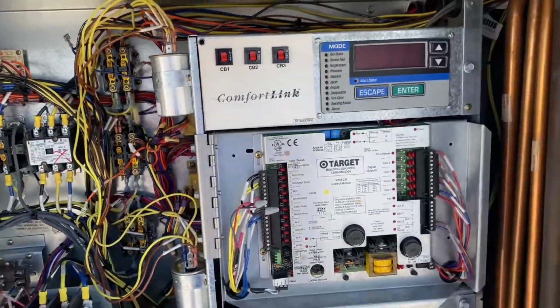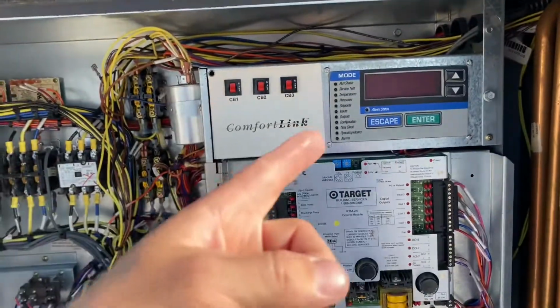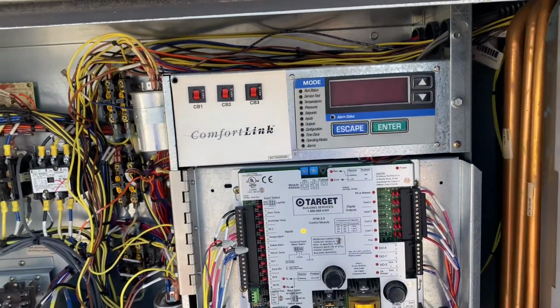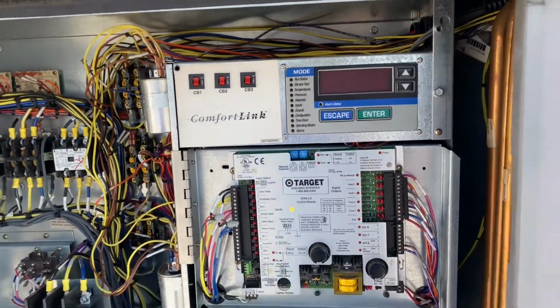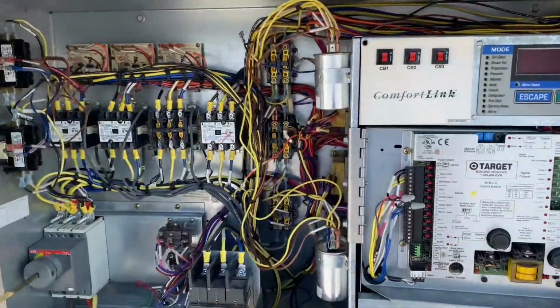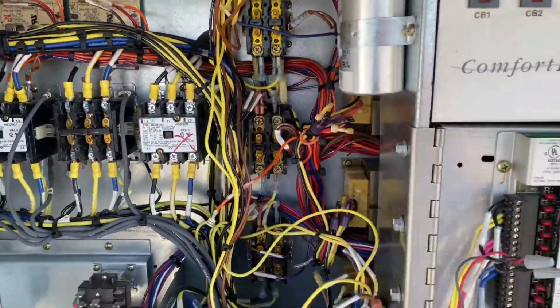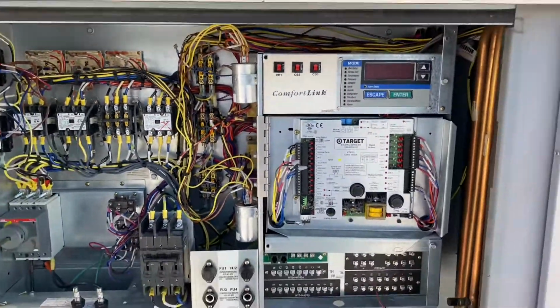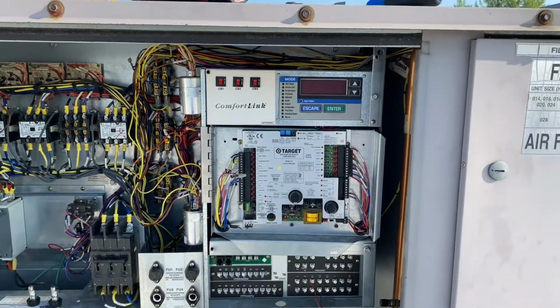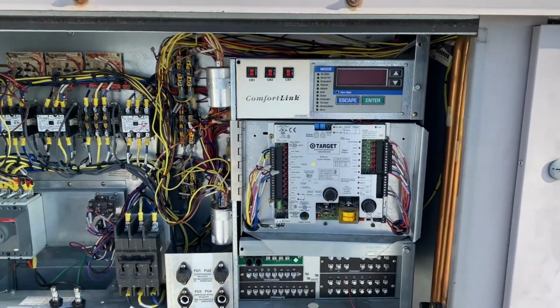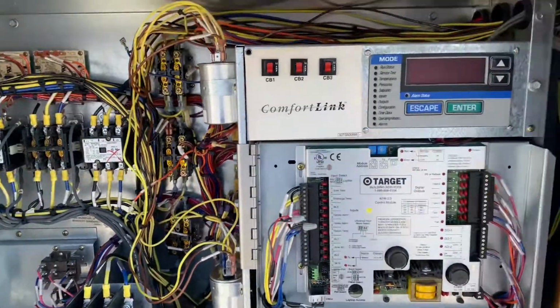And then rushed over here after I power back on, get to the controller, put it in test mode to test outdoor fan 2, well, contactor for outdoor fan contactor 2 anyway, which ended up powering fan 2 and 3 just as suspected. They cycled on. It didn't blow it right away.